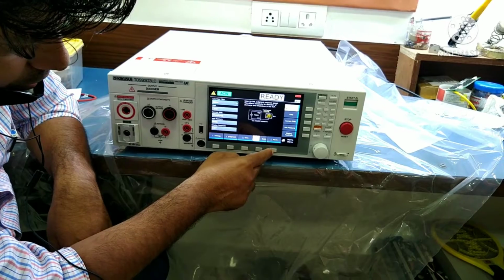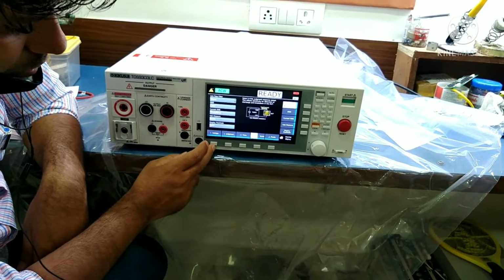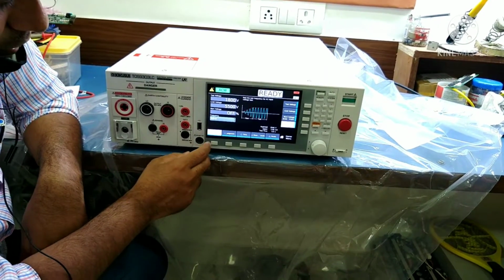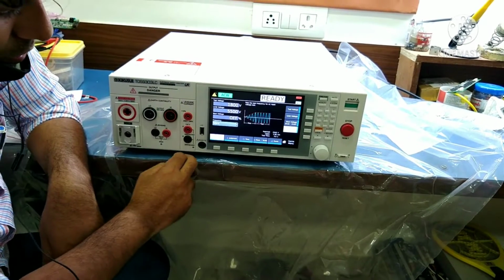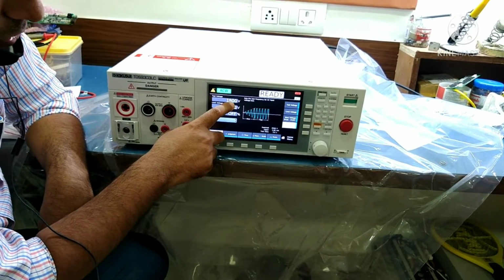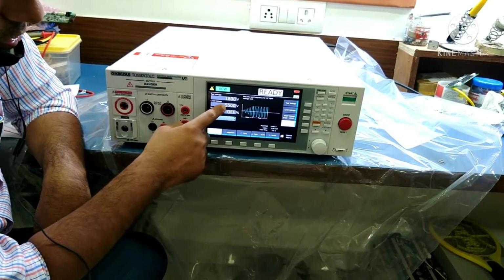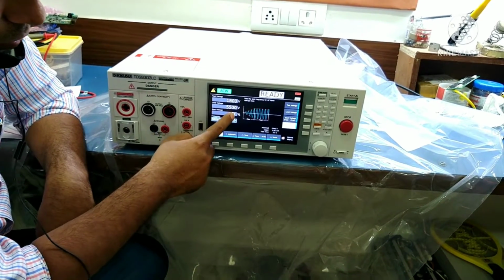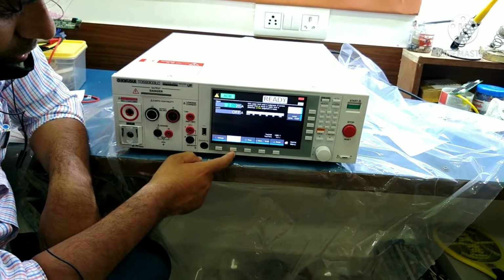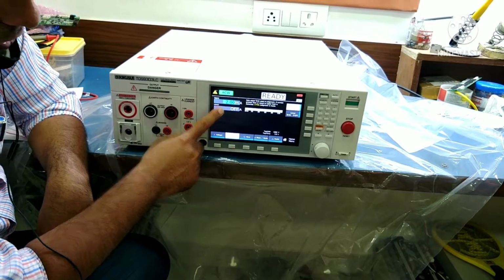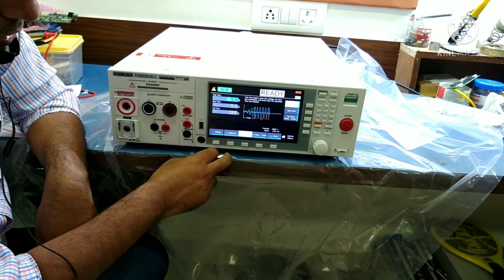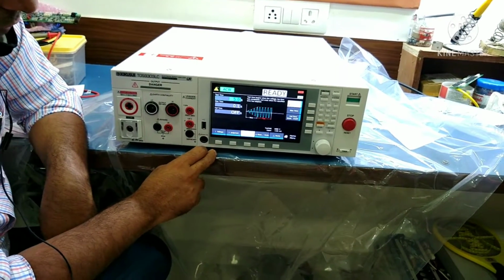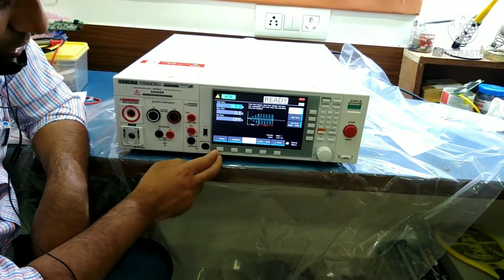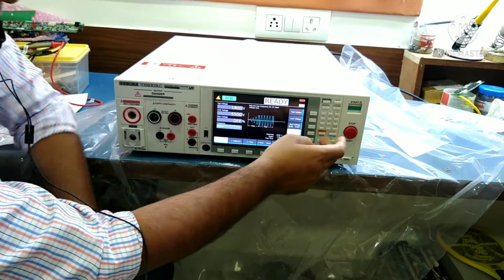This is the measurement setting, so there is no need to disturb these settings. We only need to focus on the basic settings. So I have set the voltage at 1800 volts. You can see the maximum limit, the start voltage, and the judgment upper value of 2 milliamperes. The test time is 5 seconds. It will run for 5 seconds. So let's start the test.